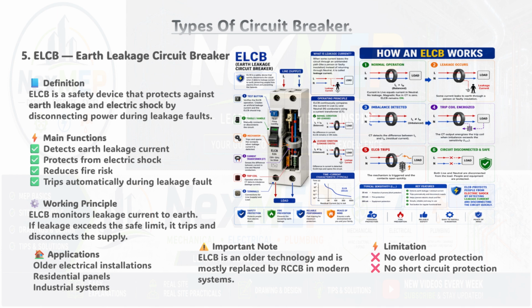You'll find ELCBs mainly in older residential panels, older electrical installations, and some industrial systems. One important thing: ELCB is older technology. It has been mostly replaced by RCCB in modern installations. And remember, it does not protect against overload or short circuit. It only handles earth leakage.